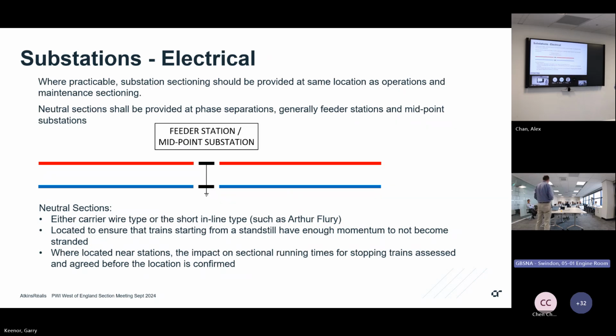One thing I think we're not very good at, and I've personally been on the receiving end of criticism from train operators for this, is finding out how neutral section location near stations affects sectional running times. Typically we do our best to locate a neutral section near a station because that's where the substation is. But after doing the design, we present to train operators and they say that doesn't work for us, it causes a major operational headache. So make sure you get the operators involved at an early stage, although it can be difficult to get engagement, but do try to make the effort.